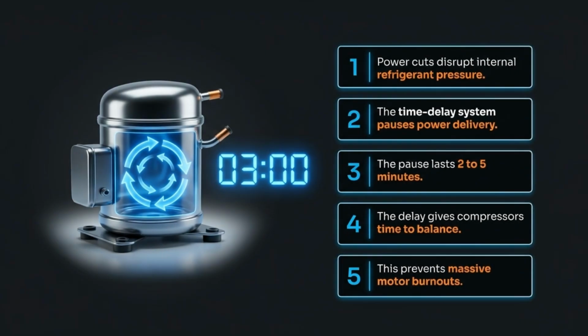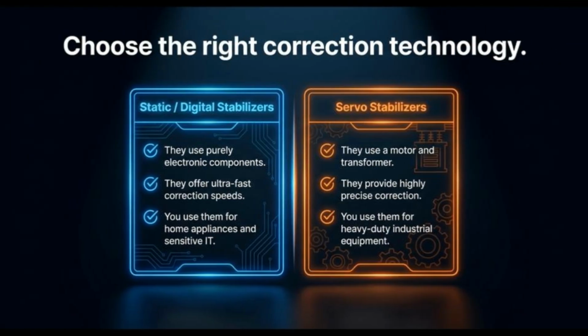Power cuts disrupt internal refrigerant pressure. The time delay system pauses power delivery for 2 to 5 minutes, allowing compressors time to balance and preventing motor burnouts. You need to choose the right correction technology. Static/digital stabilizers use electronic components for ultra-fast correction in home appliances. Servo stabilizers use a motor and transformer for highly precise correction in heavy-duty industrial equipment.